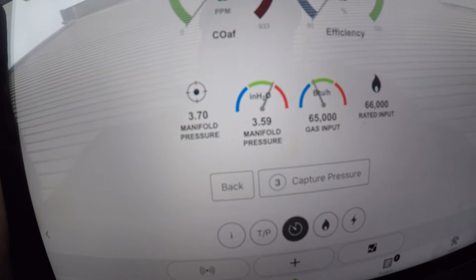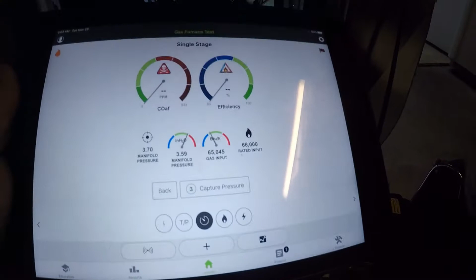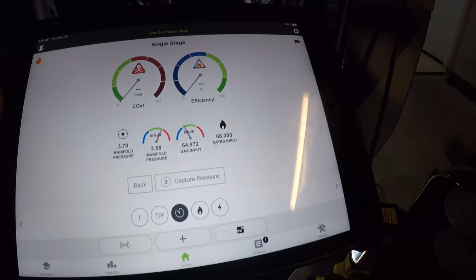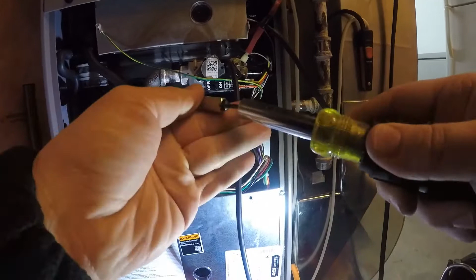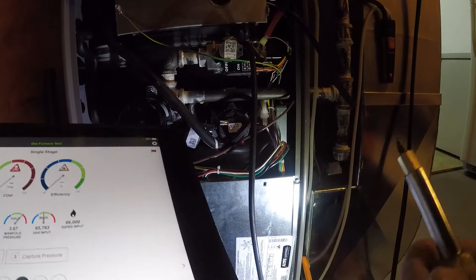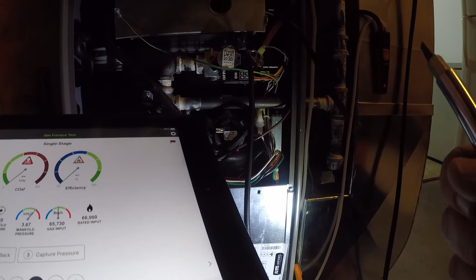Alright, so we're back at the furnace. And as I dial it into 3.7, watch what happens to my input. The whole point of these input tests are if our input was incorrect, either too much or too less, you would order new orifices, because every place around North America has a different heat content of gas.